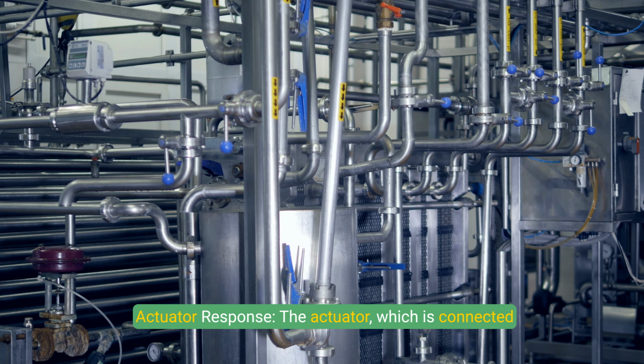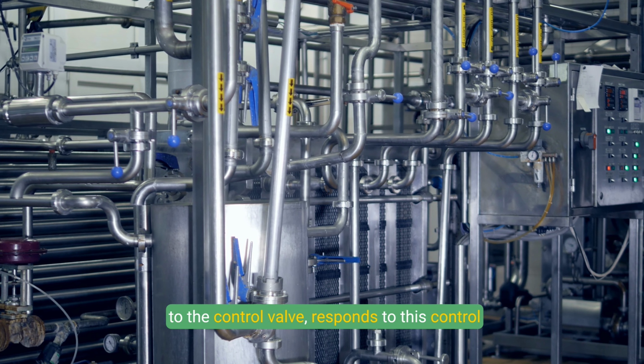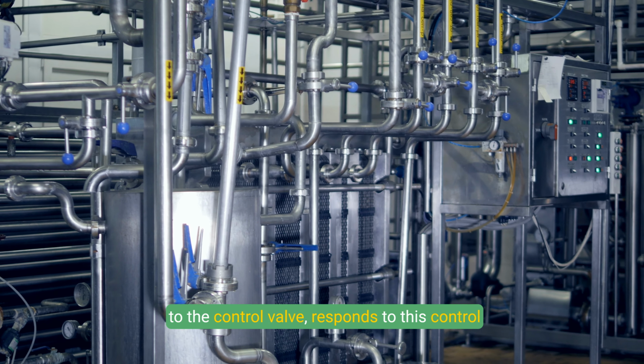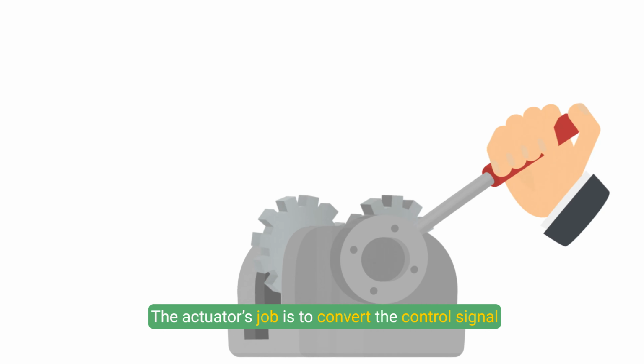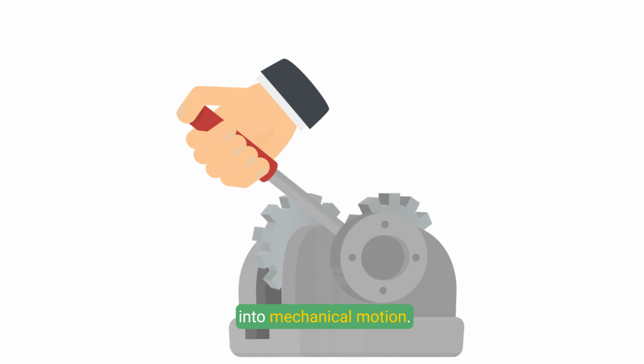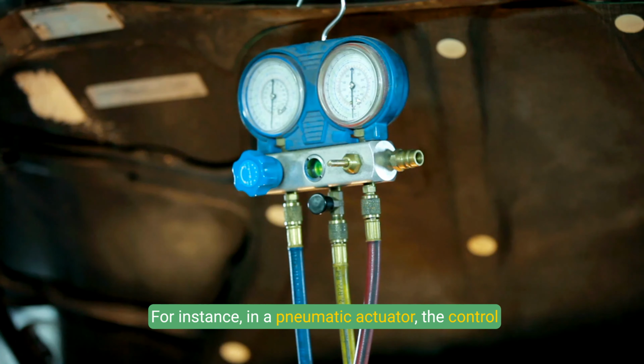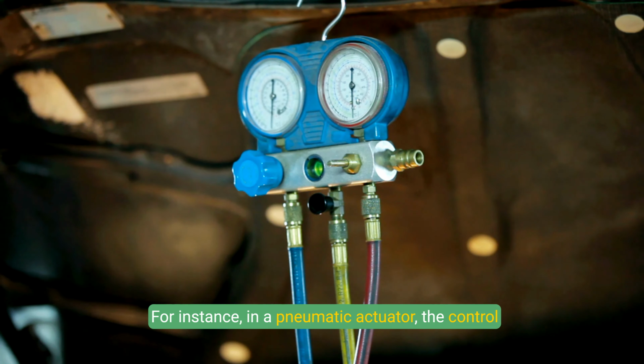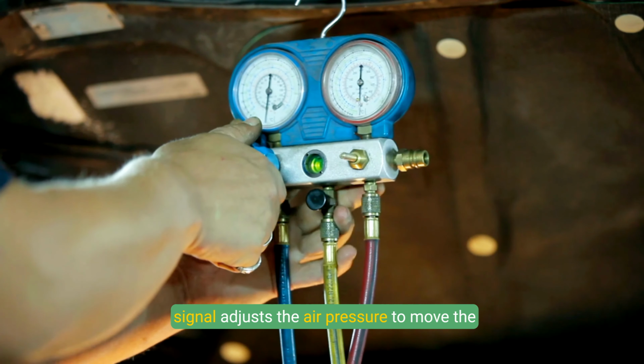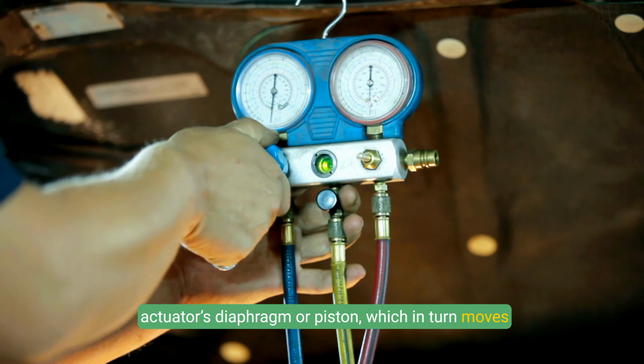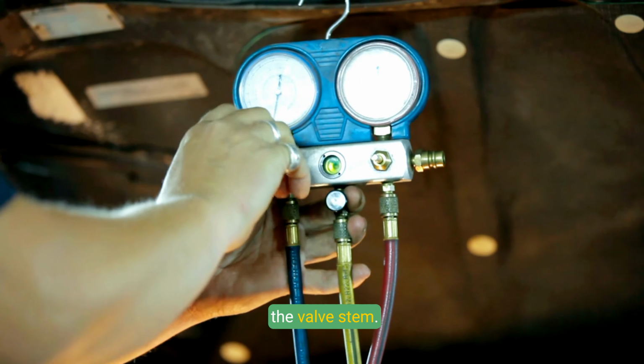Actuator response. The actuator, which is connected to the control valve, responds to this control signal. The actuator's job is to convert the control signal into mechanical motion. For instance, in a pneumatic actuator, the control signal adjusts the air pressure to move the actuator's diaphragm or piston, which in turn moves the valve stem.